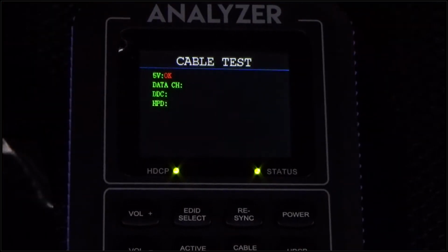Now again, this might not be pre-installation. This might be an instance where you're on site doing a retrofit job. Cables are buried inside the wall, or maybe they're zip tied in a rack and it looks really good, so you don't want to tear it apart unless you have to. But again, test all these cables beforehand in a retrofit job, test them as you go.